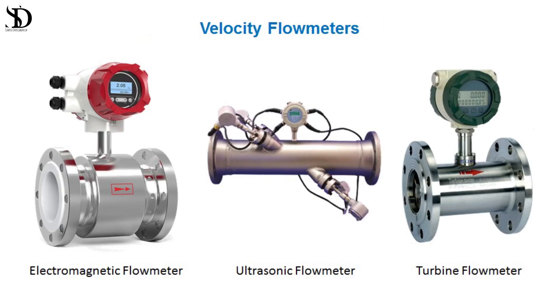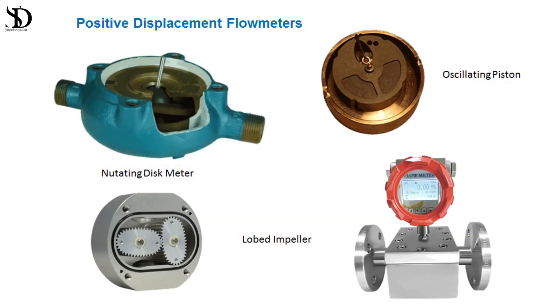2. Velocity flow meters: utilize the velocity of the fluid to determine flow rate. Examples include electromagnetic, ultrasonic, and turbine flow meters. 3. Positive displacement flow meters: these measure fluid flow by repeatedly filling and emptying a chamber of known volume. Piston, gear, and nutating disc meters are common types.